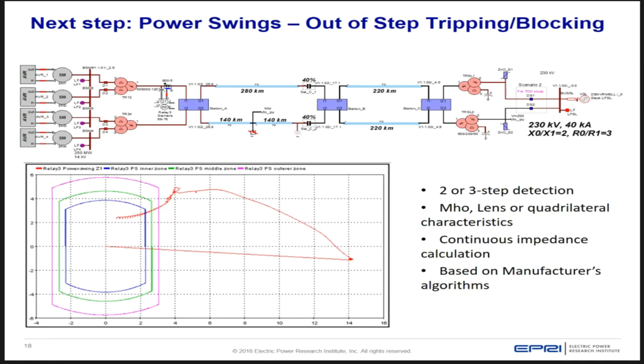Distribution folks were doing sample testing and modeling. Were you able to do that, like benchmarking? Well, we try to validate the models. We have some data from NREL that we are working on now with Thomas and others, to look at the measurements that we have from the EPRI lab. You know very well the inverters over there are 1547 inverters, and they don't have the control options that we use in these utility scale applications. So we are not using those, but we are trying to collect actual fault response measurements from different members to try to validate.